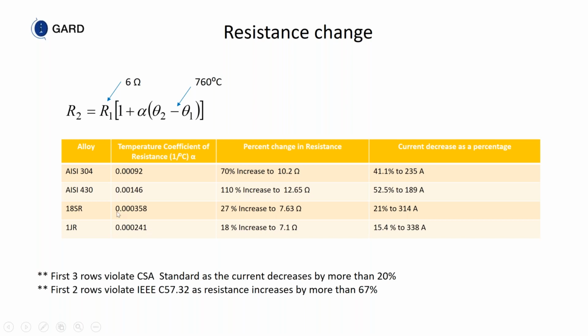As you can see, the first 3 rows violate CSA standard C22.2, number 295, because part of the testing for CSA is the rated voltage test, which basically means you apply rated voltage for rated time, and the resistance or the current shall not decrease by more than 20%. So you can see the current decreases by 41% with 304, decreases by 52% for 430, decreases 21% for 18SR, but decreases only 15.4% for 1JR.